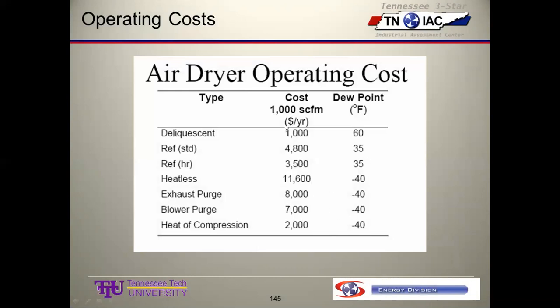The relative operating cost. This is dollars to dry 1,000 standard cubic feet per year. I think this is based on 5-cent electricity. And so you see the dew point and the relative operating cost. So see, this heatless desiccant dryer costs you a boatload, and that's because you're venting that 15%. The heat of compression is 2,000, so that's even better than the heat recovery standard dryer. This is the refrigerated dryer that just runs all the time. So you see the thermal mass reduces operating cost. But this heat of compression dryer is pretty darn good. But the problem is that you have to retrofit a compressor, or basically when you buy an air compressor, if you want that, you buy it with it.